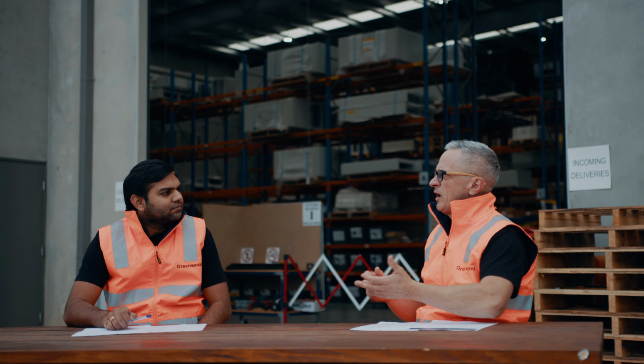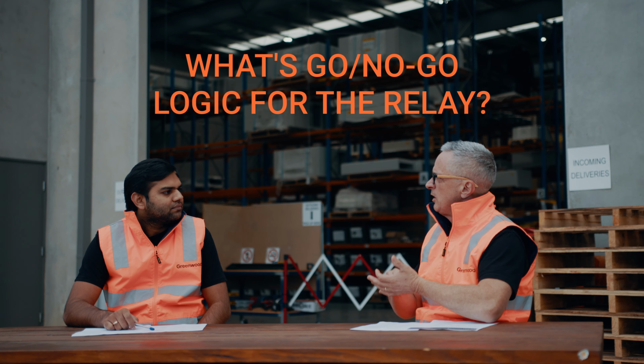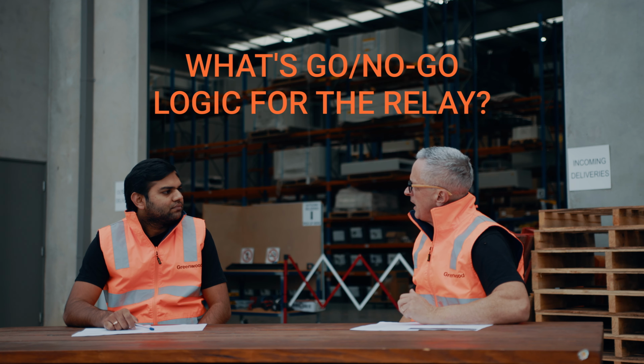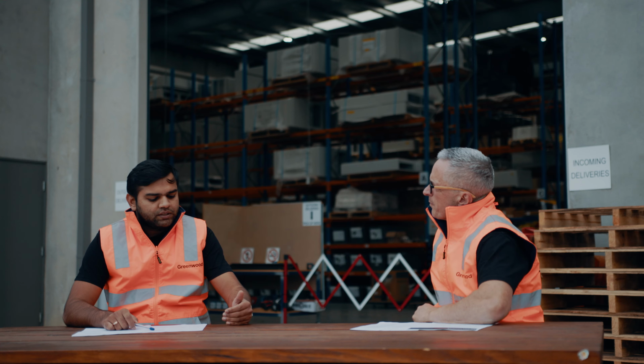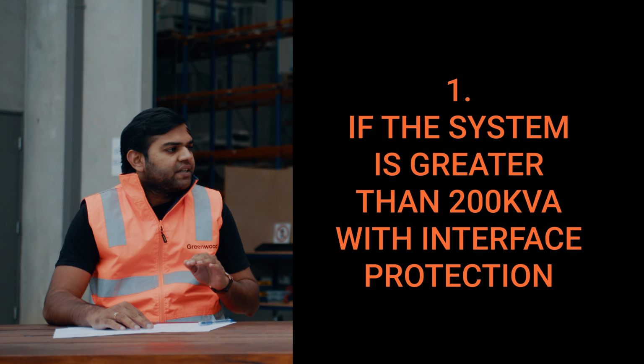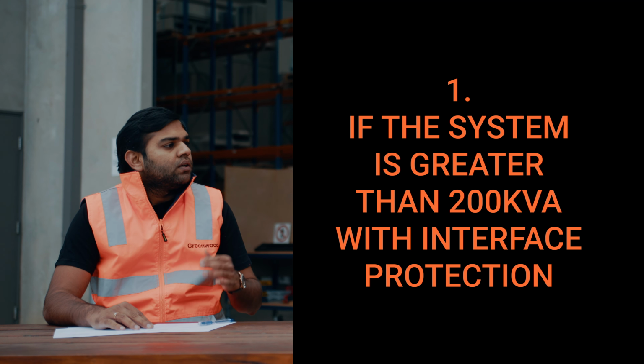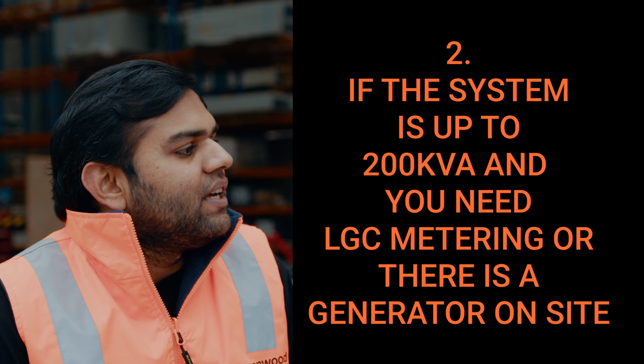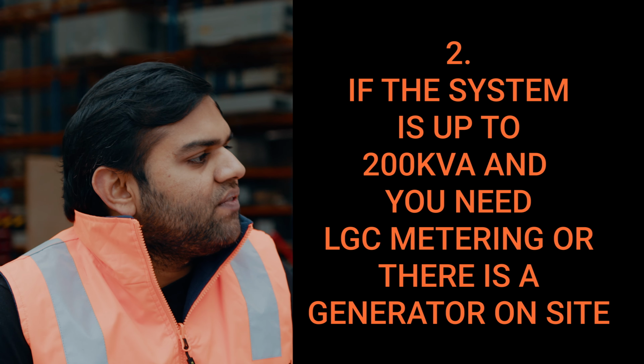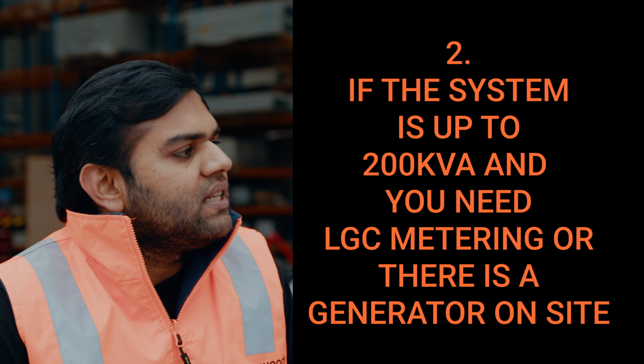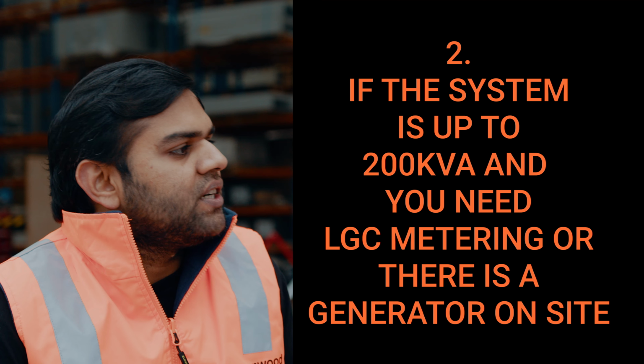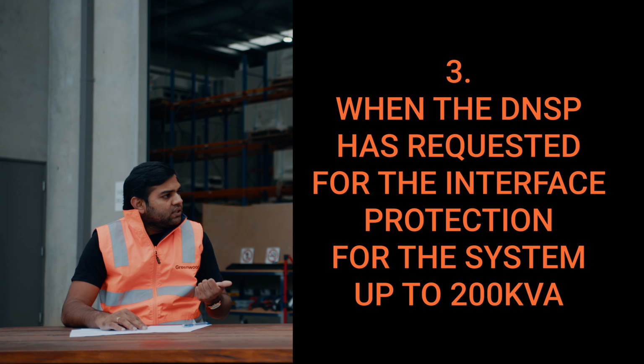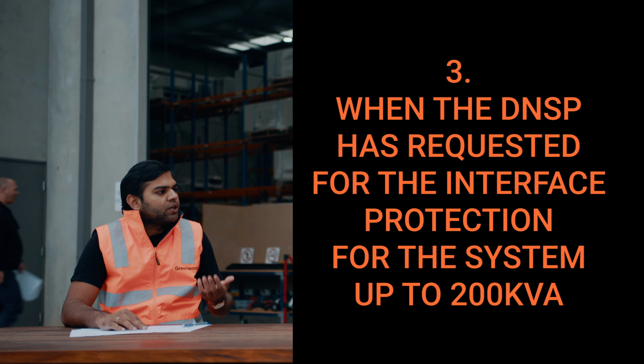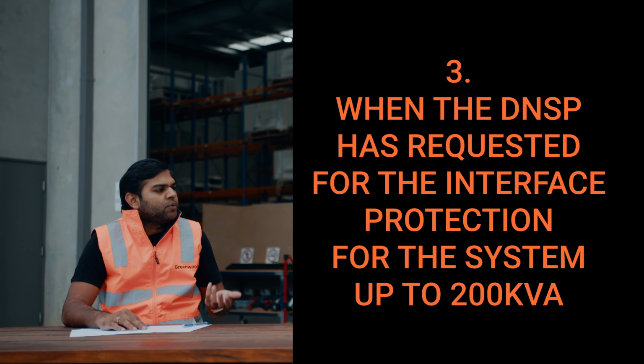Would you be able to summarise the go, no-go logic for the relay? There are 3 logics. If the system is greater than 200 kVA, a normal GridSafe board is required with interface protection. If the system is up to 200 kVA and you require the LGC metering or there is a generator at site. The third one is when the DNSP has requested for the interface protection for the system up to 200 kVA.